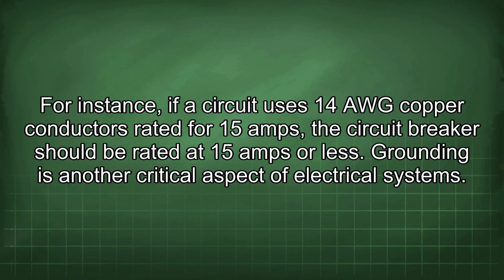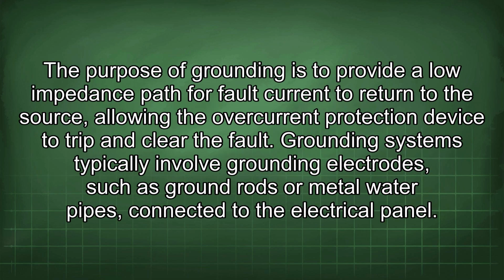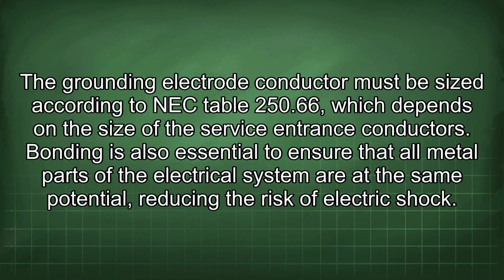Grounding is another critical aspect of electrical systems. The purpose of grounding is to provide a low impedance path for fault current to return to the source, allowing the overcurrent protection device to trip and clear the fault. Grounding systems typically involve grounding electrodes, such as ground rods or metal water pipes, connected to the electrical panel. The grounding electrode conductor must be sized according to NEC Table 250.66, which depends on the size of the service entrance conductors.